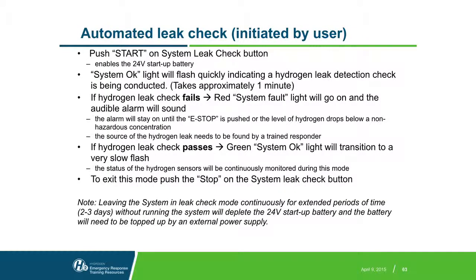During the leak check, the operator will use this system leak check button here and hit start. And there's a series of flashing lights. We'll have a summary on this, but basically the system OK light will quickly flash, indicating a leak detection check is taking place. If it fails, then the red light will go on and the alarm will sound. Someone can push an e-stop, or if the alarm stops sounding, then the hydrogen level has dropped below a detectable level, and theoretically the hazardous condition has mitigated itself. But we still need to figure out where the leak is coming from.